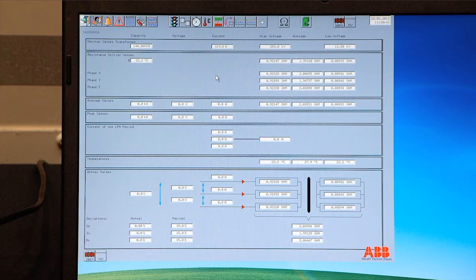This is done at the frequency set in value F201. The measured resistance in the HV winding is sent to the PLC and is stored together with the calculated low voltage resistance. These values, together with the average voltage values, are used as the reference for the entire process. The following values are checked or calculated. The variation of the resistance distribution over all phases is checked and calculated. The deviation of resistance measures in sequence is measured and calculated.